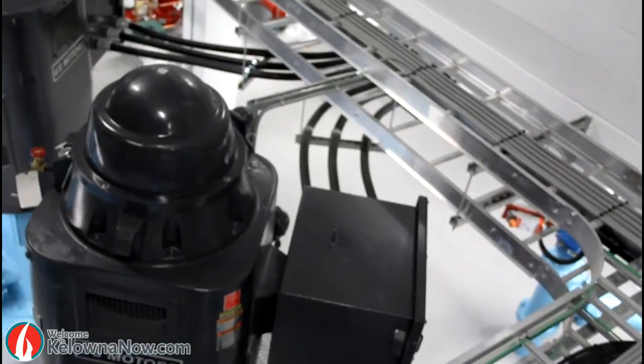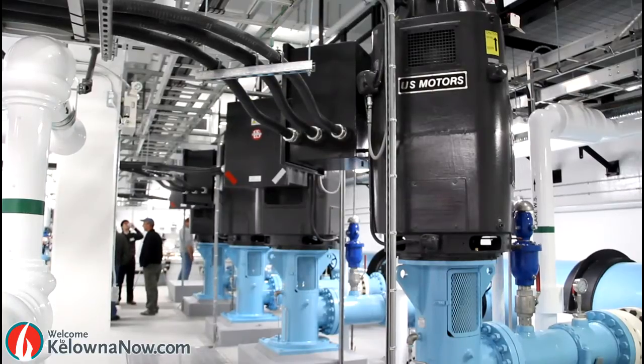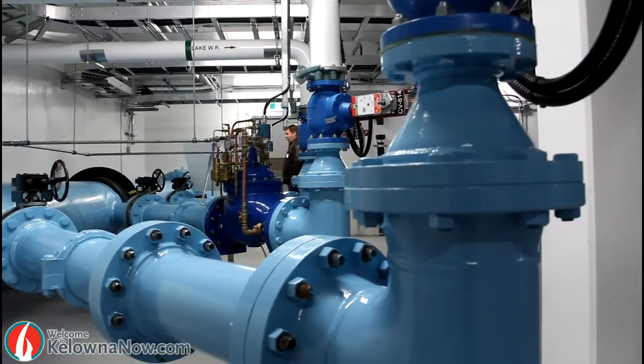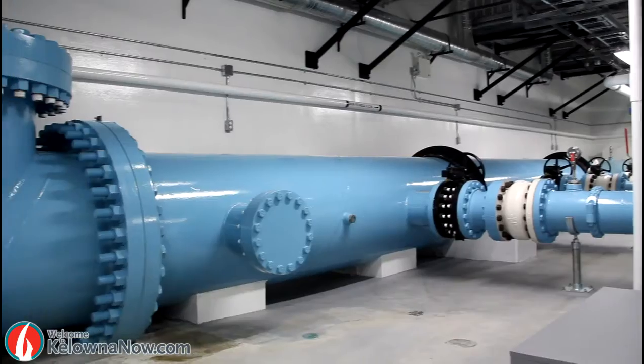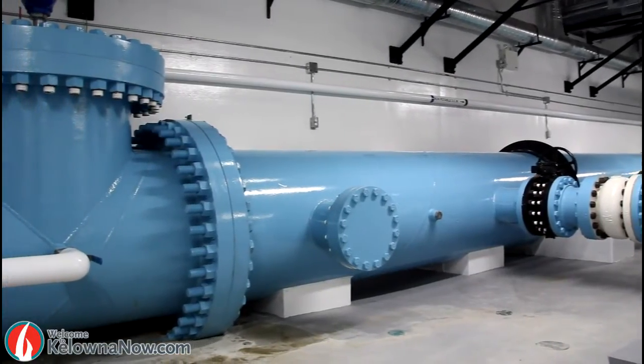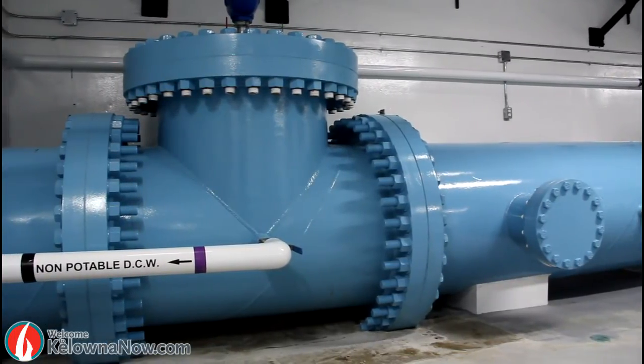What we have here is four 700 horsepower electric motors. These pumps are capable of pumping 3,600 gallons per minute. They pump through this discharge manifold, which pumps up to the McKinley Reservoir. The idea is to pump the raw lake water into McKinley Reservoir where it will be treated through chlorination at our McKinley Chlorinator.